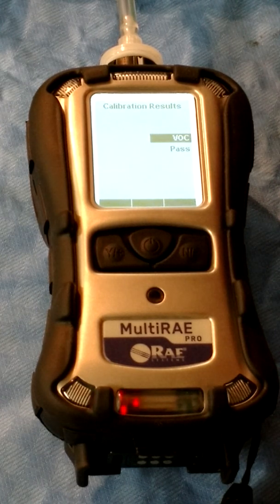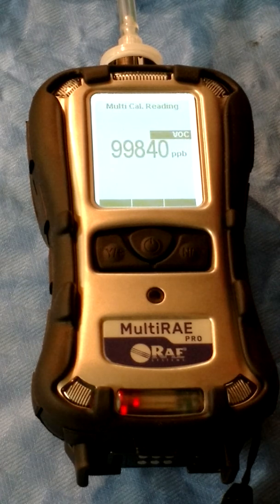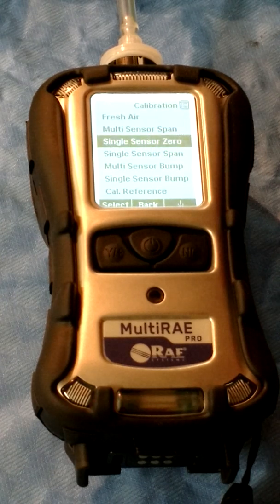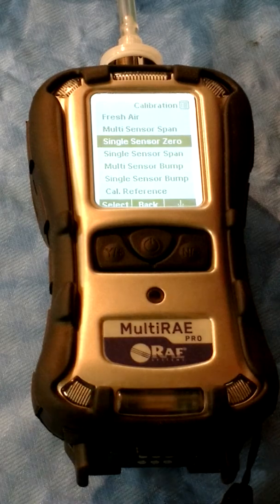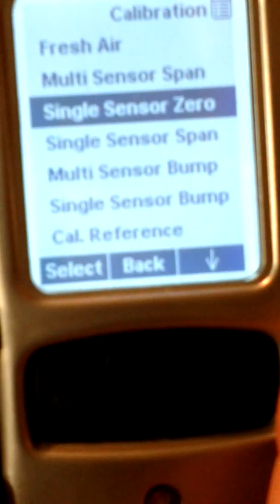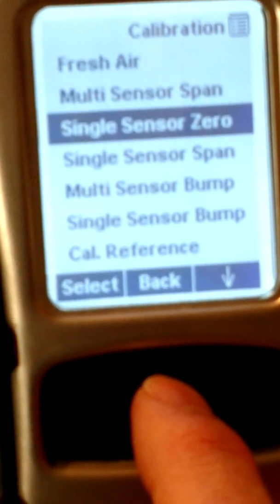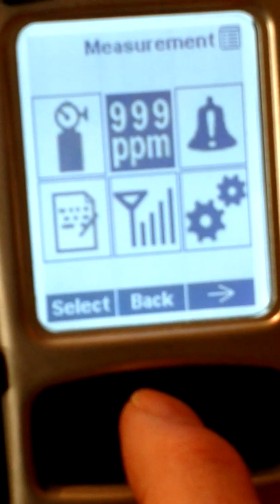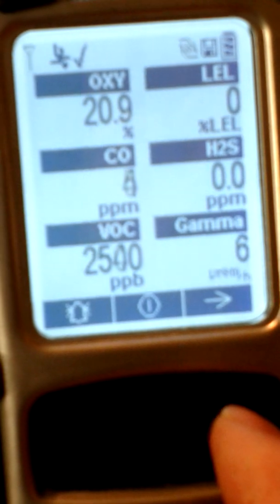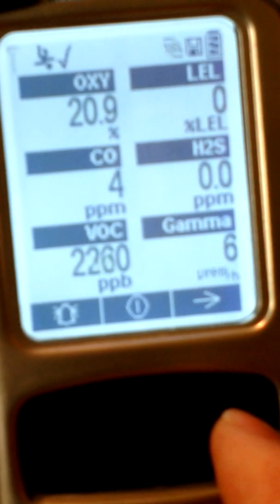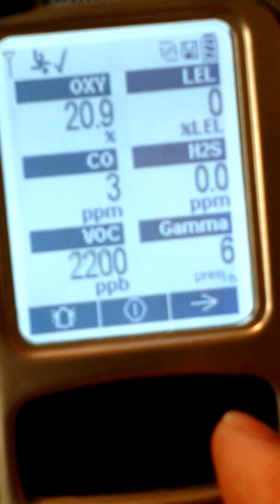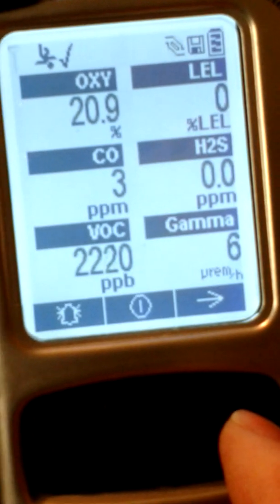So another pass for the VOC, and approximately 100 ppm or 99,000 plus ppb. We'll remove the gas now, turn off the valve. Now we're going to press the mode back button. Back again, and as mentioned, after the meter purges itself, we'll perform a fresh air calibration and we'll be done.